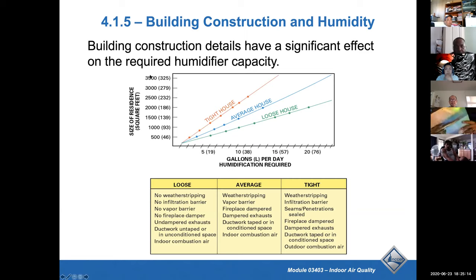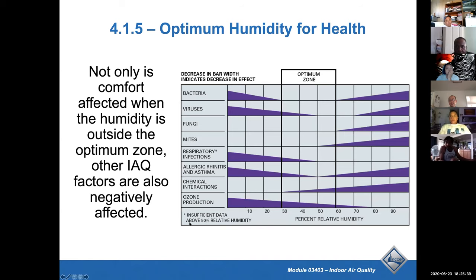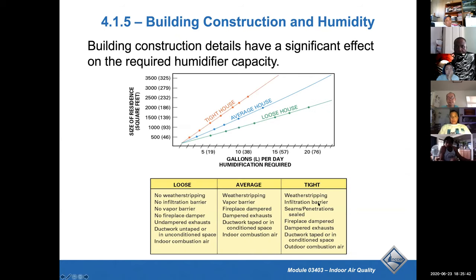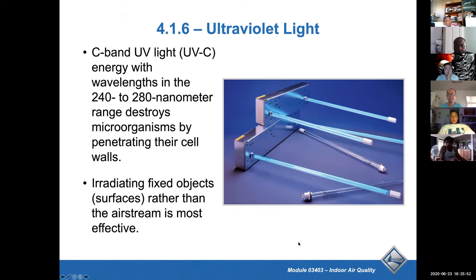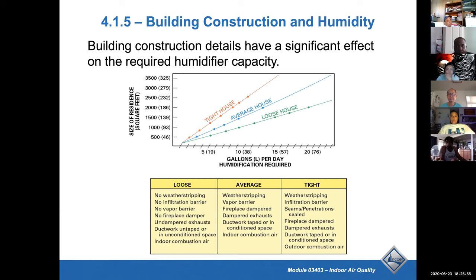Building construction has a significant effect on required humidifier capacity. Size of residence, and what your humidification required. Loose, average, and tight, and it tells you all the construction materials. Loose is basically a shack, no weather stripping, no vapor barrier, no fireplace damper. And the tight one would be weather stripping, infiltration barrier, seams and penetrations sealed, fireplace damper, dampered exhaust, duct work taped or in conditioned space, and outdoor combustion air.